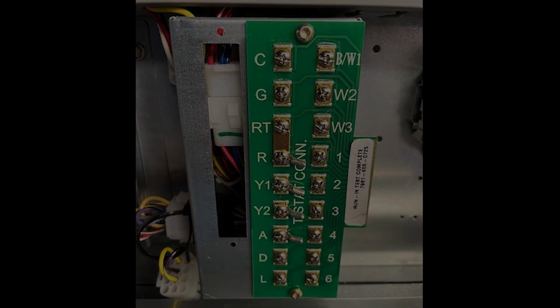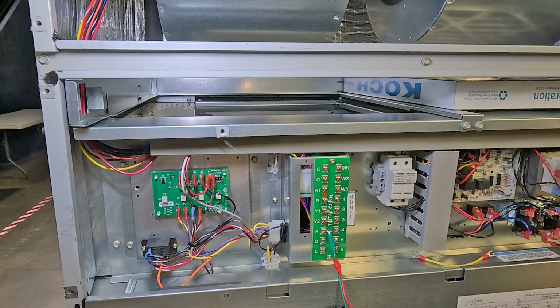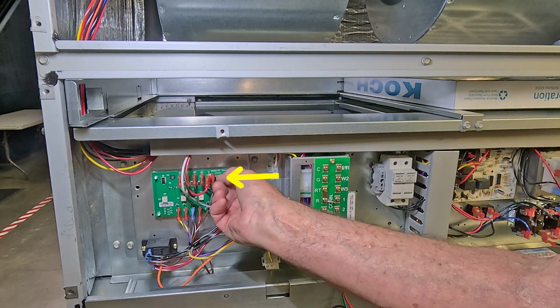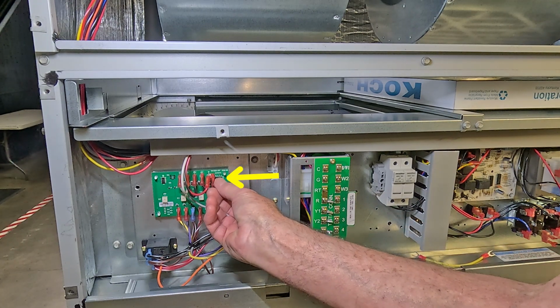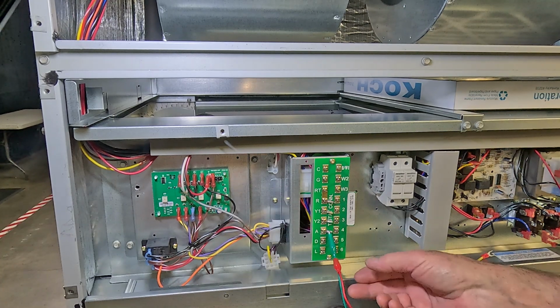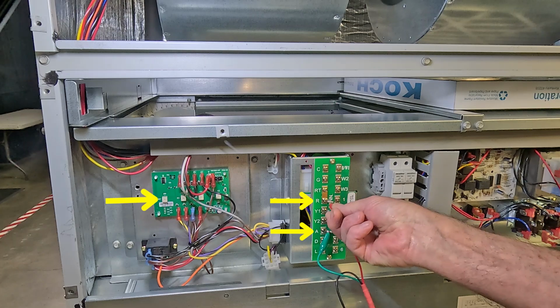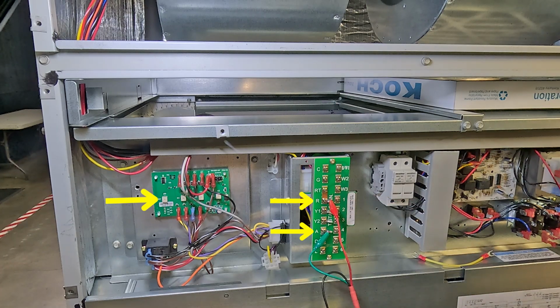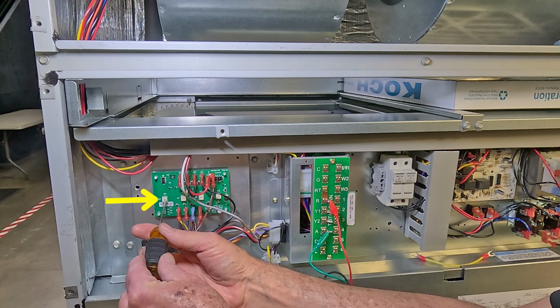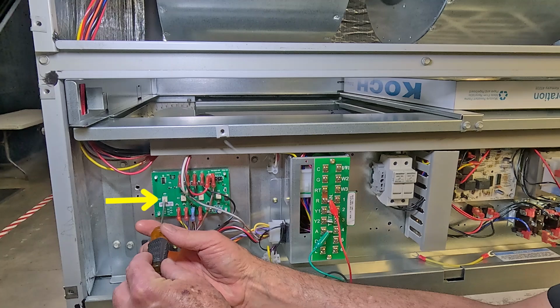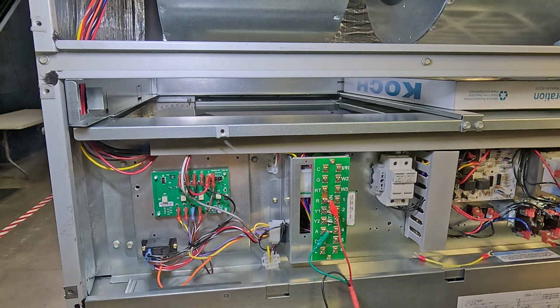Next, on the optional pre-purge pot, on the pre-purge timer, move the little black jumper from 0 to 60 first, before energizing the board. Jumper wire R to A and turn pot PP clockwise until the damper stops at 6 on the decal. To get 3 complete pre-purge air changes in 60 minutes in a California classroom, the damper needs to be set for 450 CFM. This also means that A must be energized 1 hour prior when pre-purge is used. Then PP and OCC work together.